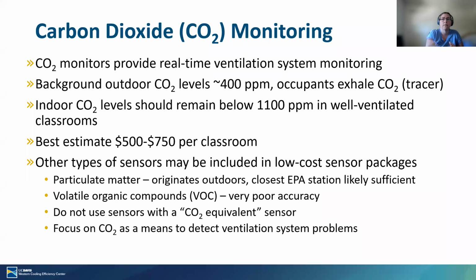Volatile organic compound sensors that are included in low-cost packages are very poor accuracy. So it could create a false sense of alarm for no reason. And so just really focusing on CO2 is really the most useful measurement for continuous ventilation system monitoring.